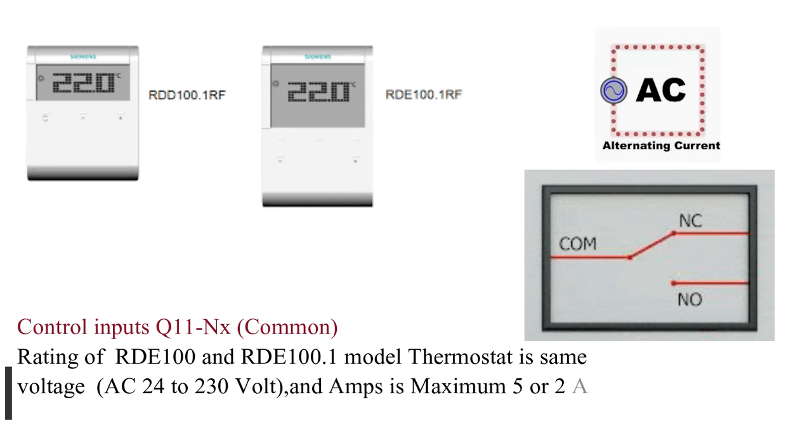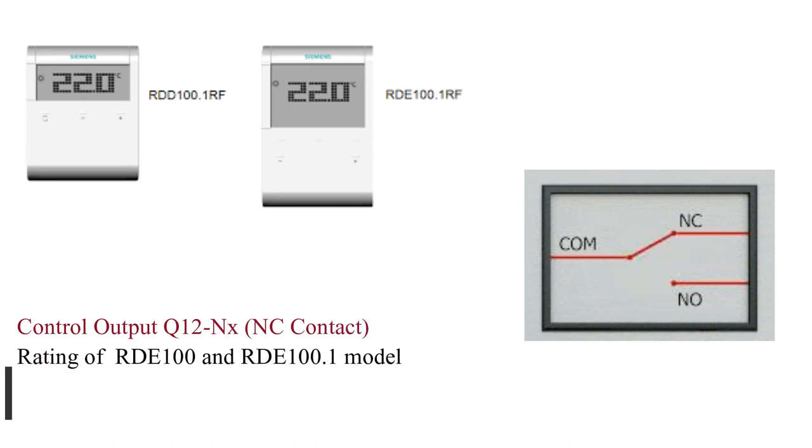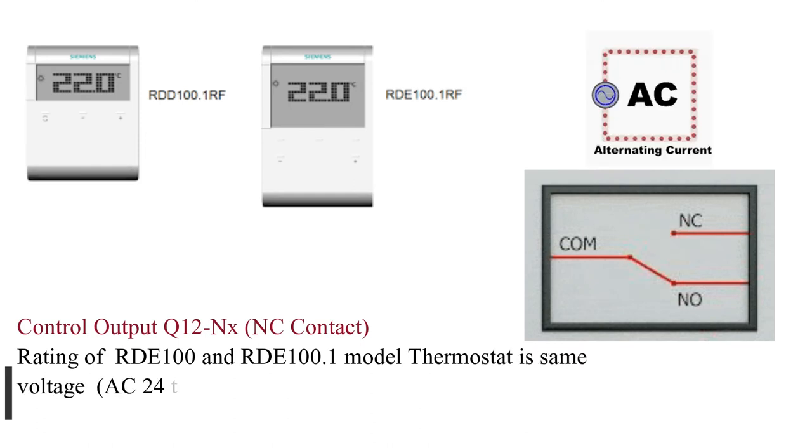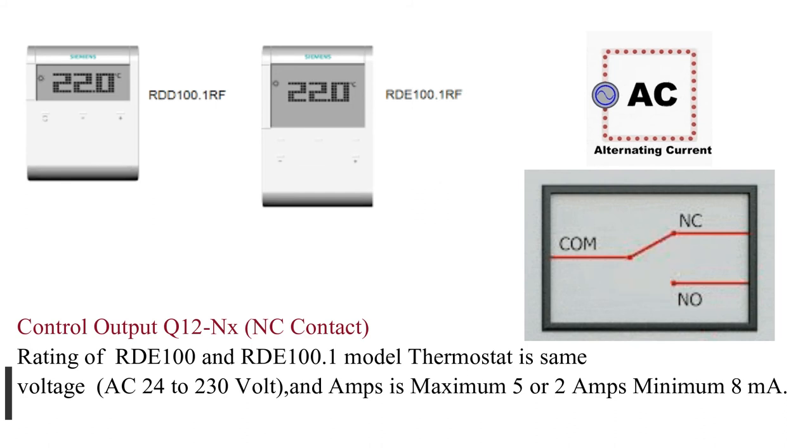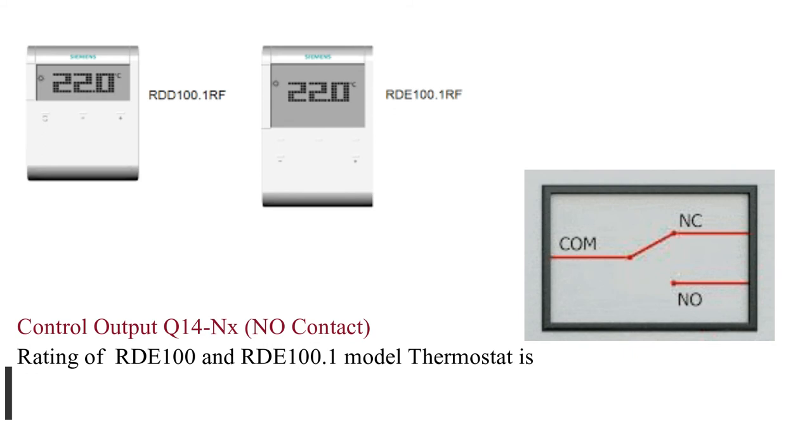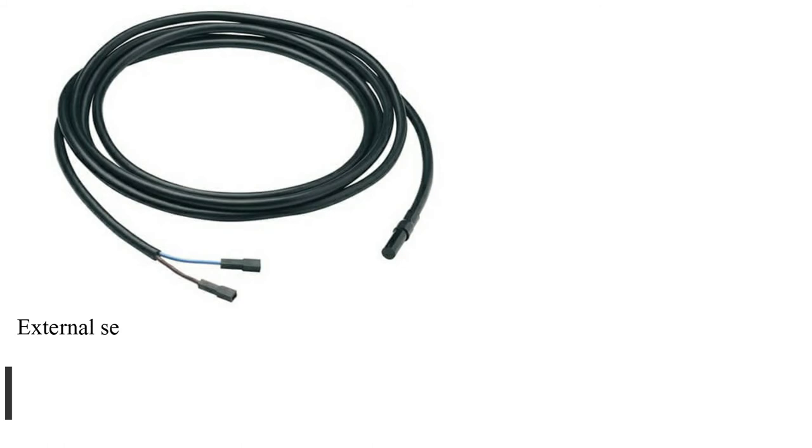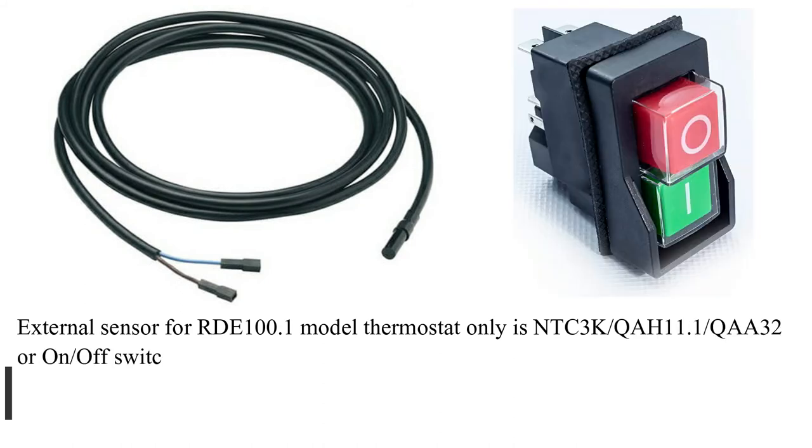Control output Q12NX NC contact: Rating of RDE100 and RDE100.1 model thermostat is same voltage AC 24 to 230V, and amps is maximum 5 or 2 amps, minimum 8 milliamps. Control output Q14NX NO contact: Rating of RDE100.1 model thermostat is same voltage AC 24 to 230V, and amps is maximum 5 or 2 amps, minimum 8 milliamps. External sensor for RDE100.1 model thermostat only is NTC3K/QAH11.1/QAA32 or on/off switch.